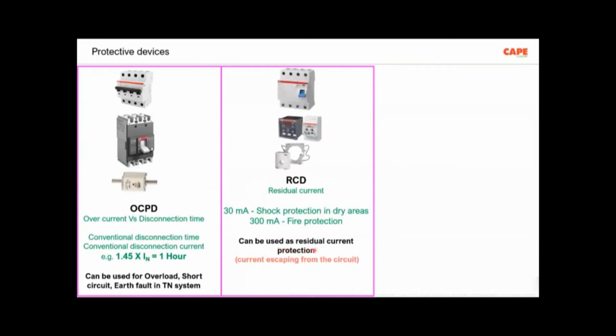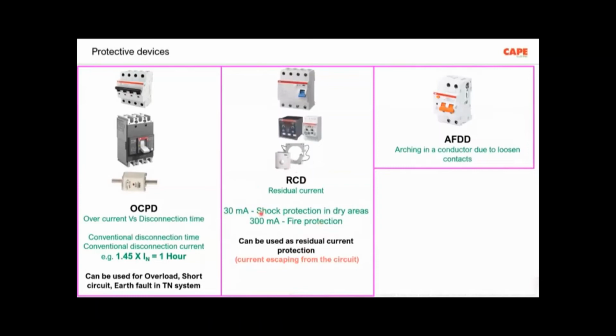So these devices can be used as a residual current device. For non-electrical engineers, I have put a tricky way: current escaping from the circuit. So residual current is the current which is not flowing through a circuit. It is actually escaping from the circuit due to some insulation failure or some leakage. So if the current escaping from the circuit is more than 30 milliampere, your RCD trips. This is what I mean by RCD, and these devices can be used only for earth fault protection, not for overload and short circuit protection.